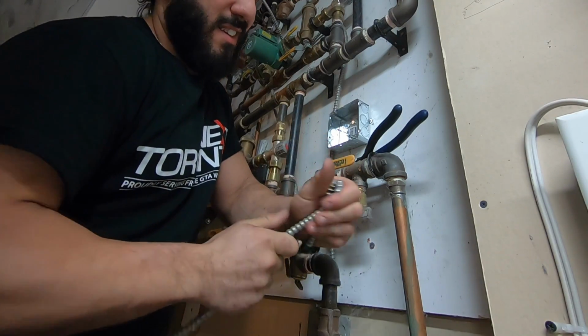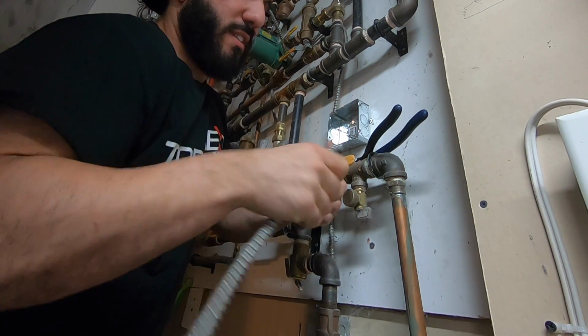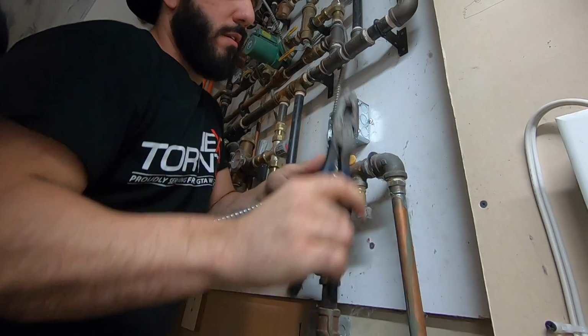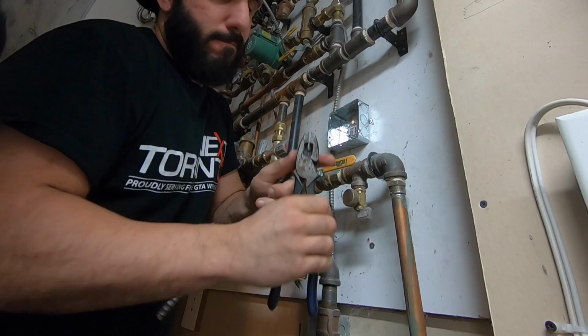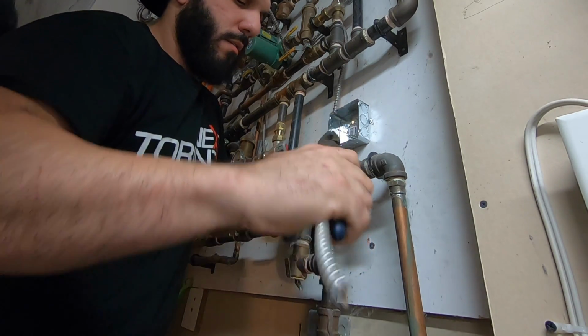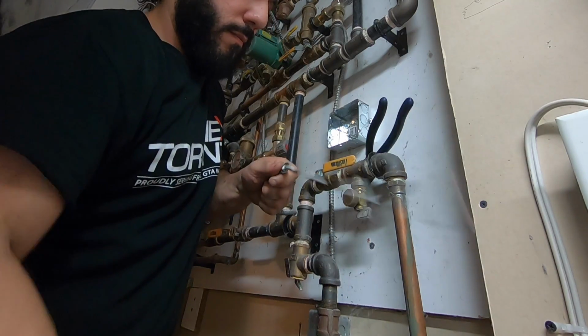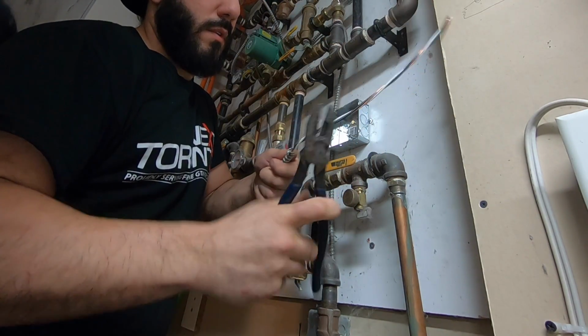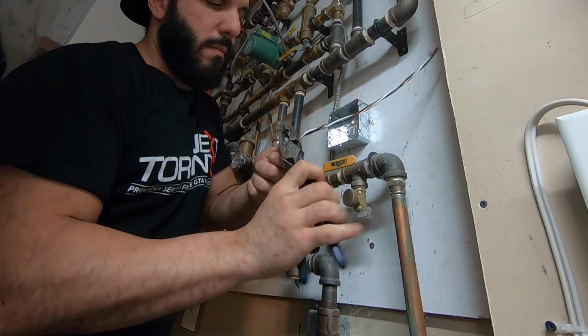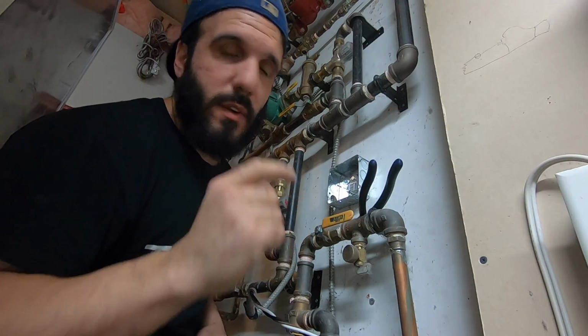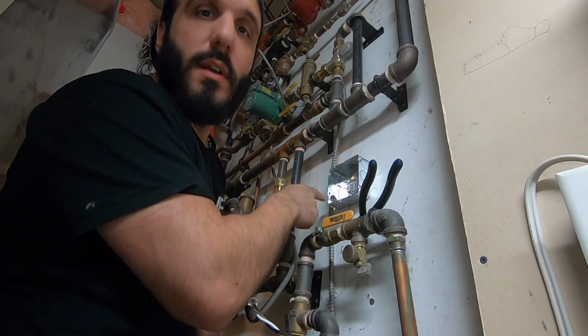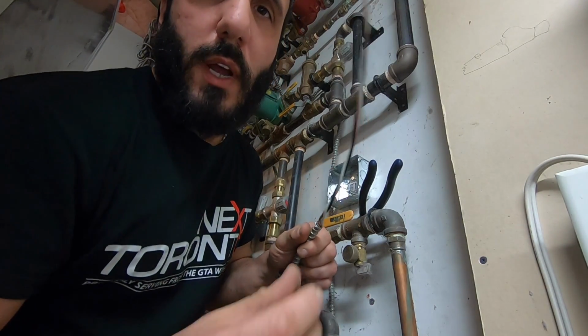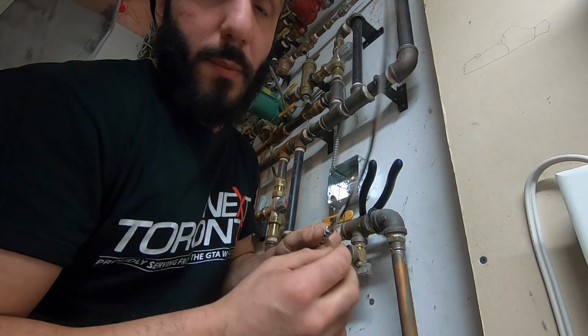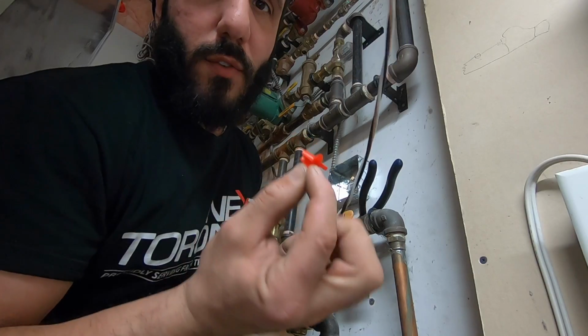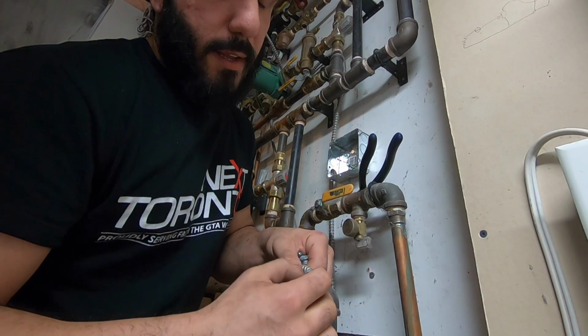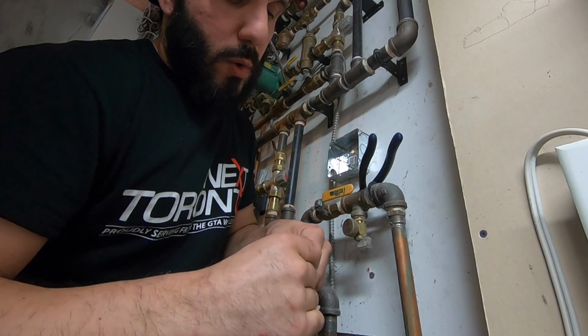This BX, just snap it. Twist. I use linesmans. Cut it off. Clean it up. There's an unwritten rule that power always comes on the left-hand side. So by code, guys, when you're working with this stuff, the BX armored flex, you gotta stick one of these anti-shorts in between here, sheathing and the wires. It's code, electrical code.